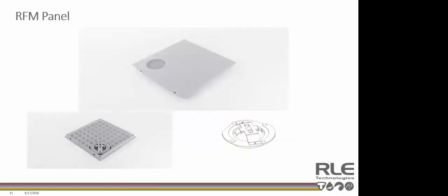In addition to wing sensors for monitoring, RLE also has integrated the wing sensors into our floor panels. The RFM panel, which stands for Raised Floor Monitoring Panel, is perfect for helping to maintain or monitor contained aisles. Ideal for differential air pressure and airflow monitoring and compatible with all RLE's suite of wing sensors, RFM panels keep reliable quality monitoring safely tucked into your raised floor system. Use these panels to understand static pressure loss or fluctuation, balance cooling airflow, and increase the available data points to understand the needs of your facilities.